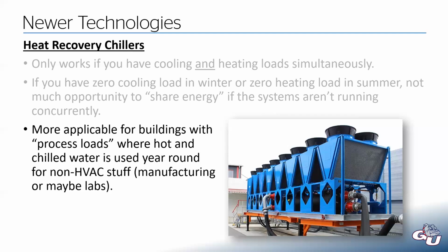And you might need that hot water year round, or you might need chilled water year round, even in the peak of winter, because whatever you're doing in that manufacturing plant or that lab needs chilled water all the time. So that would be a good example for when a heat recovery chiller could actually save you a lot of energy. And the savings are kind of twofold. You're saving it on the chilled water side because now you're not having to run your cooling tower to reject that heat outside, and you're not having to run your boiler as much because you're getting the heat from the chilled water side.